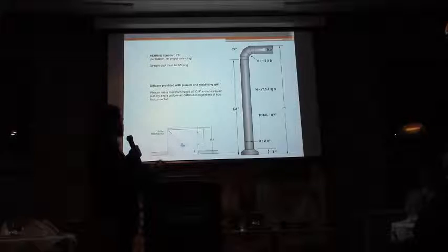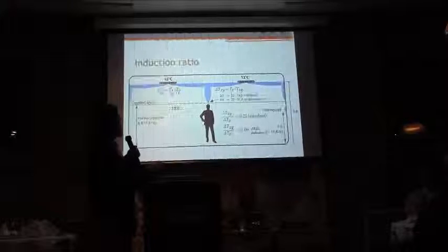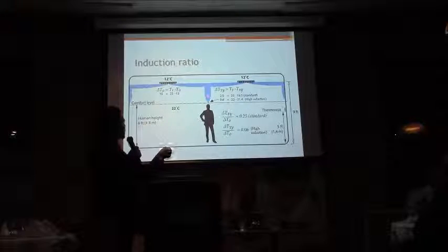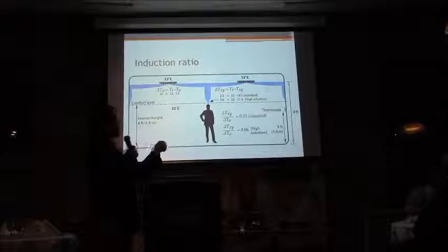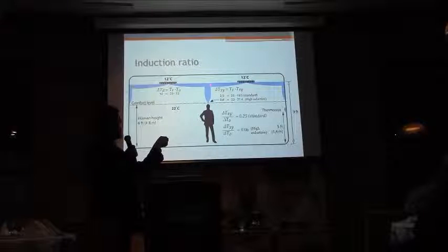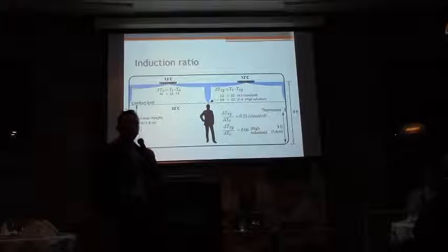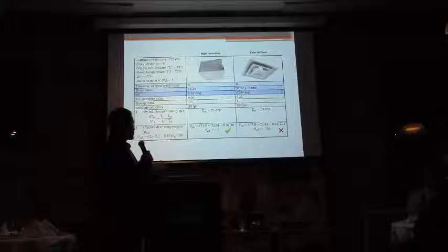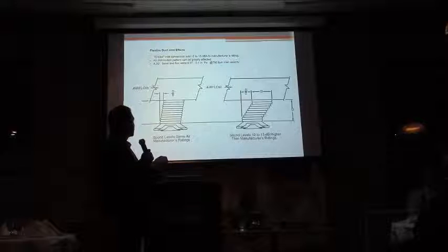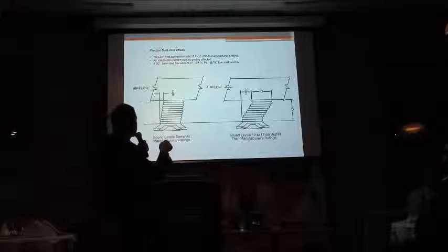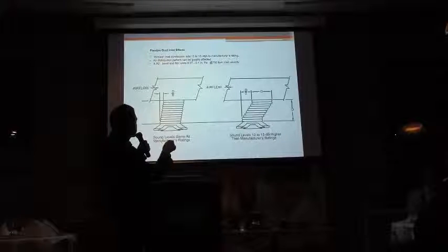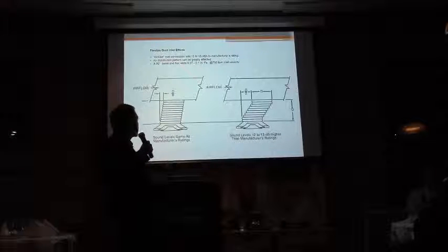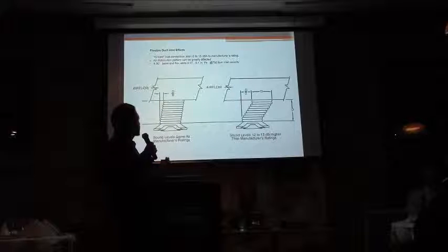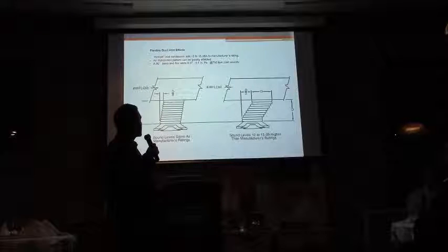So if we go back to this drawing here, imagine we calculated a maximum of 50 feet per minute, and this one is throwing 80% of the air that way, and this one is throwing 80% of the air that way. You're going to have high velocities in this zone. And the third one is that a 90-degree bend and flex adds 0.07 to 0.1 inches of static pressure at 700 feet per minute inlet velocity.